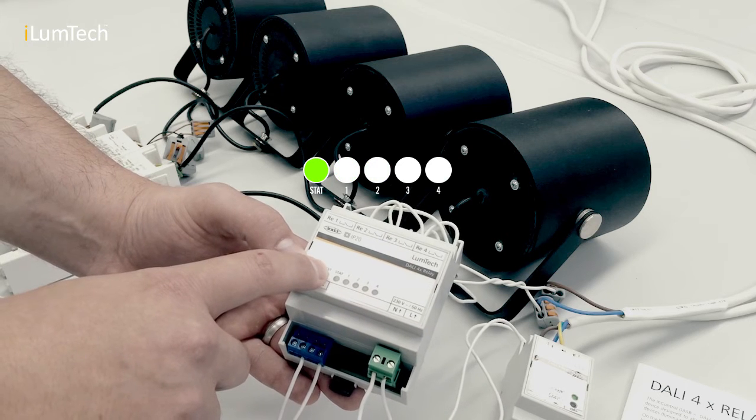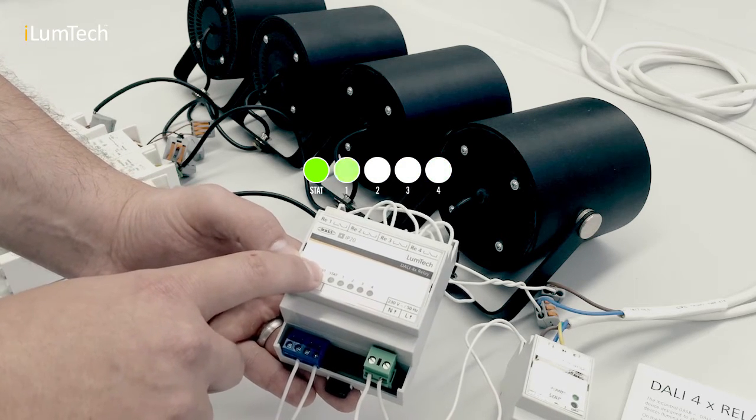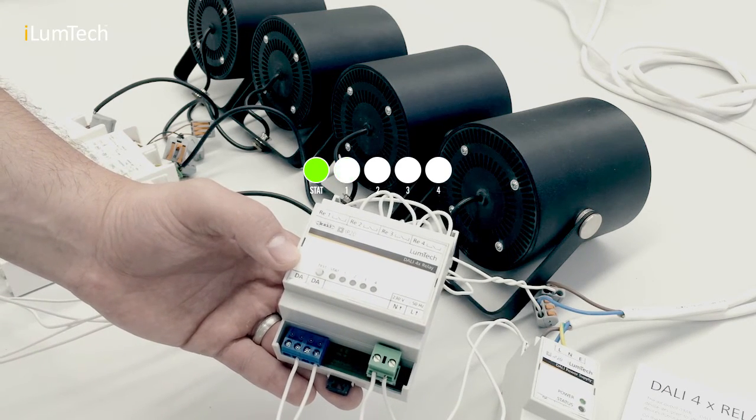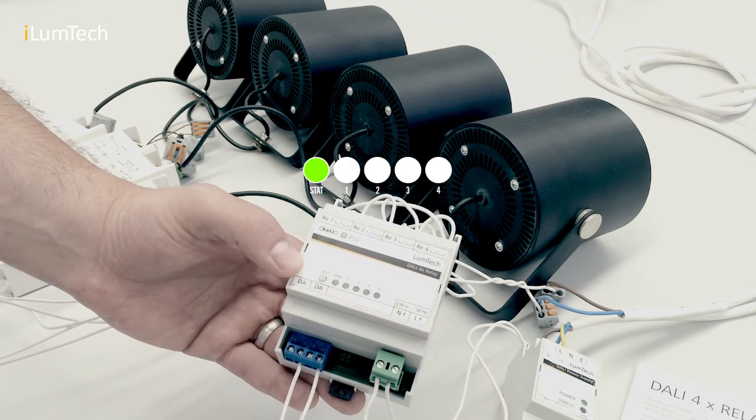Manual control mode overrides DALI control immediately after pressing the push button. DALI control is restored again after five seconds of push button inactivity. This is indicated when the LED indicator of the selected relay stops flashing.